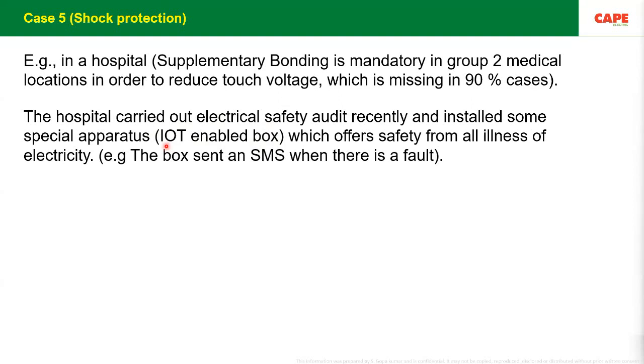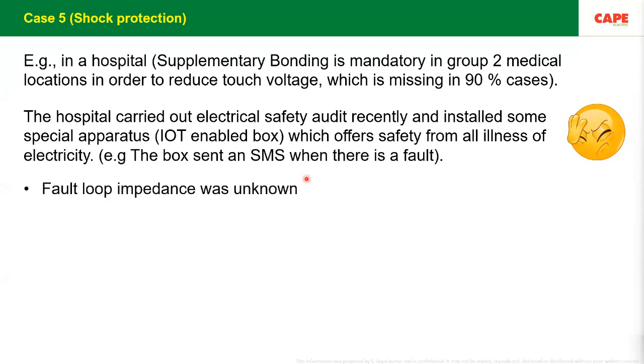And one of the safety features which they have told me is that this particular device, the box, will send an SMS when there is a fault. That means there is an insulation failure. Immediately the technician will get an SMS, and by the time he gets it, he has to go to the panel board and rectify the fault. This is what they think. But it is really a pathetic situation. Before you get an SMS, it can catch fire. Before you get an SMS, people can die. Such idiotic boxes are used across India.